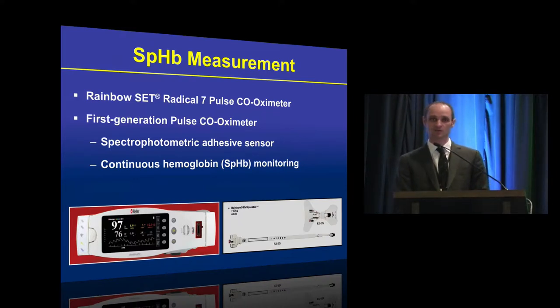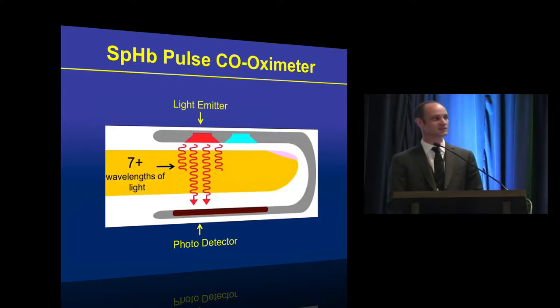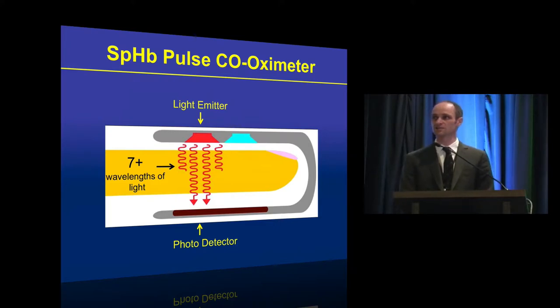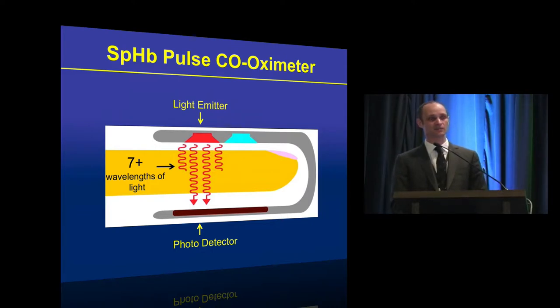How does the sensor work? Embedded in the sensor is a light emitter which sends out more than seven different wavelengths of light. After accounting for absorption within pulsatile and non-pulsatile tissue, any light that gets through is detected at the level of the photodetector. Then using a proprietary algorithm embedded in the processor within the device, it computes the hemoglobin concentration non-invasively.